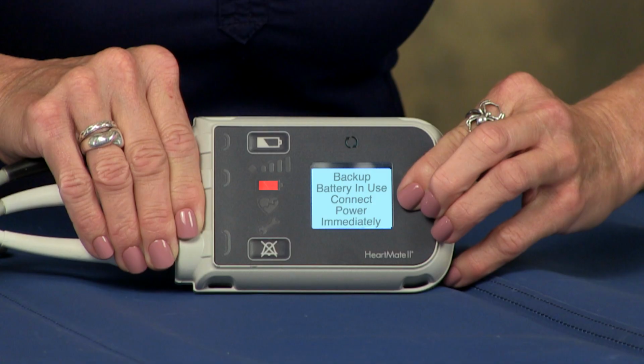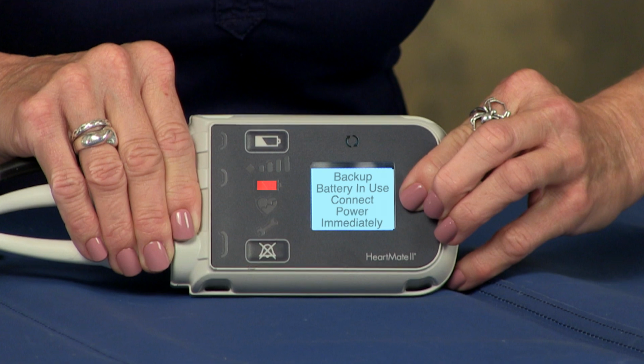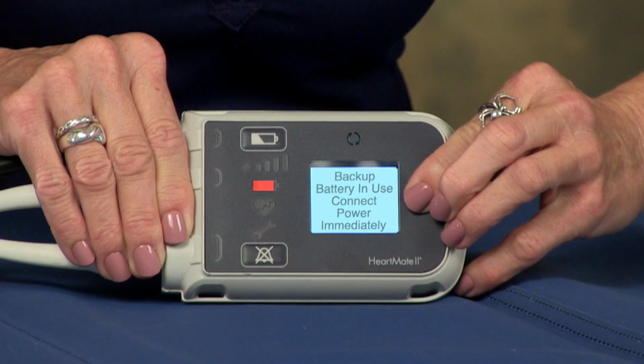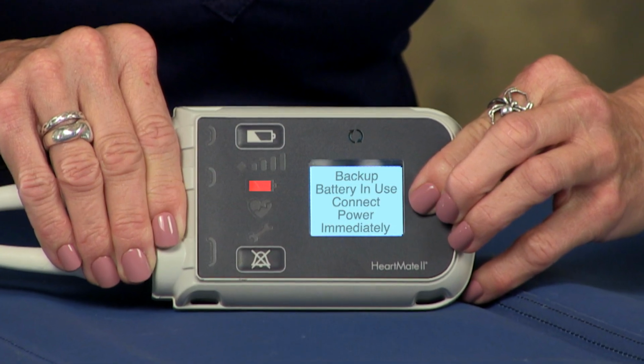If the red battery alarm is ignored, a continuous, loud, irritating alarm will sound and more lights and a demonstrative message indicating the backup battery is now in use and to connect power immediately. After this alarm occurs, the pump speed will begin to decrease in order to conserve power. Remember, the backup battery is like an airbag. We know it's there, but we don't want to use it. It's for emergency purposes only. So, as soon as the yellow diamond alarm occurs, change the batteries one at a time.